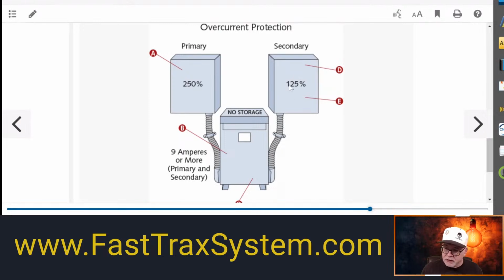You with me? So we'll assume that we sized everything. We assume we sized the transformer amps that we needed based on any continuous loads out here that are being supplied at 125%, and any non-continuous loads at 100%. Assuming we did all that, we sized our transformer because we know what we need from a transformer. Then we say, well, we're going to just make this thing a 300, even though we know that this transformer can't put out but 208 amps. There's no code violation to that.